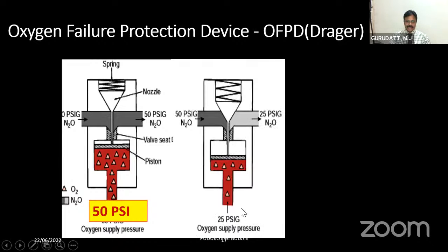So let us see, once the pressure of oxygen starts decreasing. So here I have shown you that 25 psig. What will happen is the piston starts coming down. With that, the nozzle also will start coming down. So this nozzle partially obstructs the tube that the nitrous oxide is flowing through. And once there is a narrowing of this tube, we all know the Bernoulli's principle, where when the gas encounters a narrowing through a tube, the pressure drops and the velocity increases. Here the same thing occurs. The pressure also proportionately comes down to 25 psig of nitrous oxide.